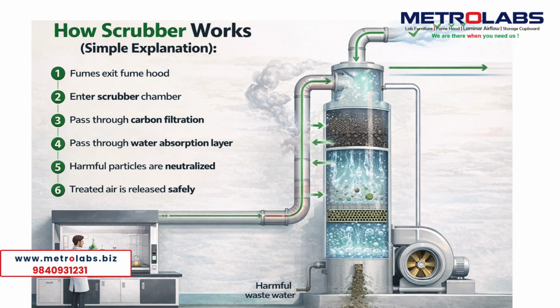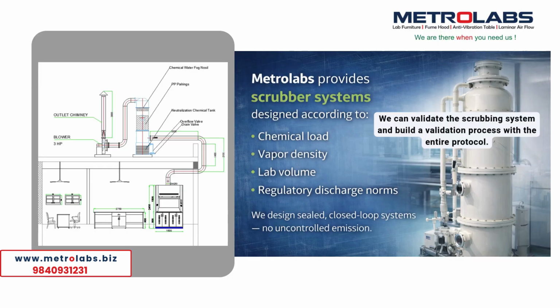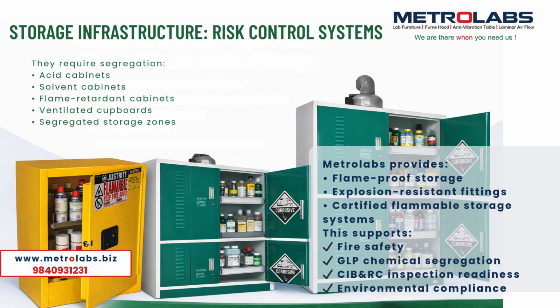This is not furniture. This is environmental engineering. Metrolabs provides scrubber systems designed according to chemical load, vapor density, lab volume, regulatory discharge norms. We design sealed closed-loop systems, no uncontrolled emission. We can validate the scrubbing system and build a validation process with the entire protocol. Storage infrastructure, risk control systems. Chemicals are not normal inventory. They require segregation. Acid cabinets, solvent cabinets, flame retardant cabinets, ventilated cupboards, segregated storage zones. Metrolabs provides flame-proof storage, explosion-resistant fittings, certified flammable storage systems. This supports fire safety, GLP chemical segregation, CIB and RC inspection readiness, environmental compliance.